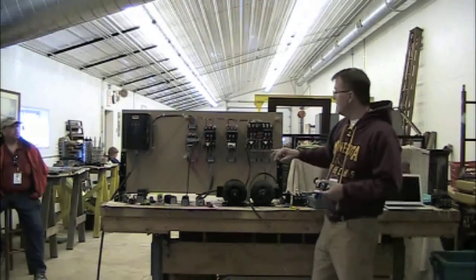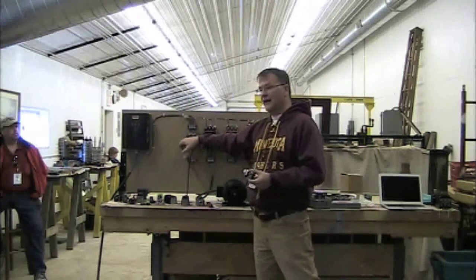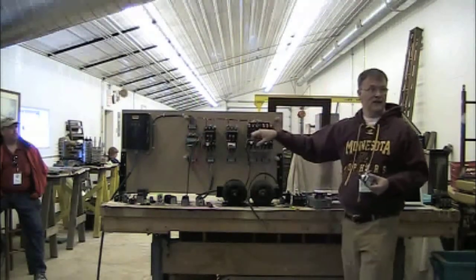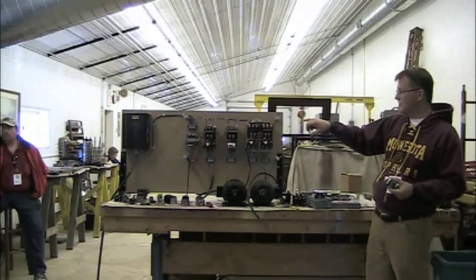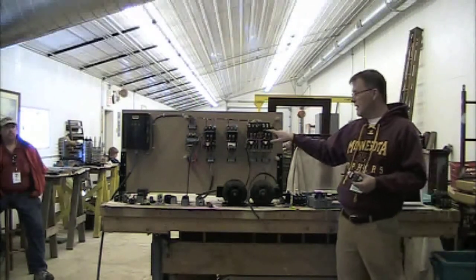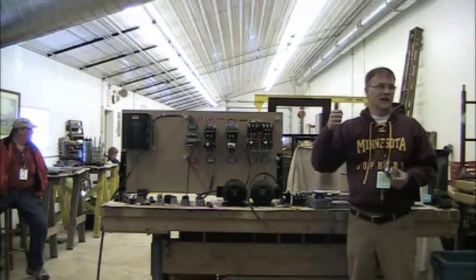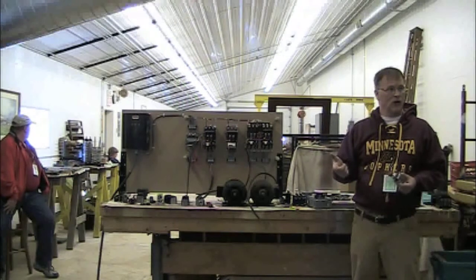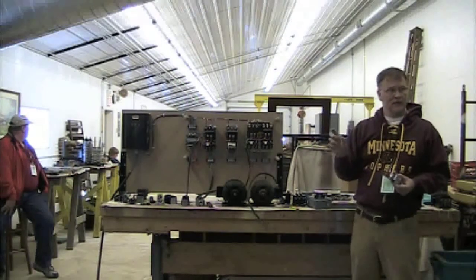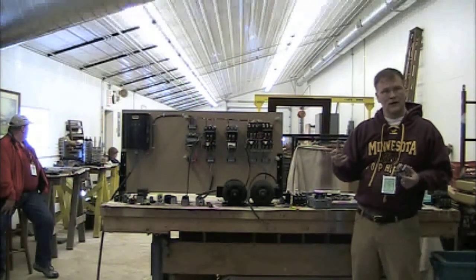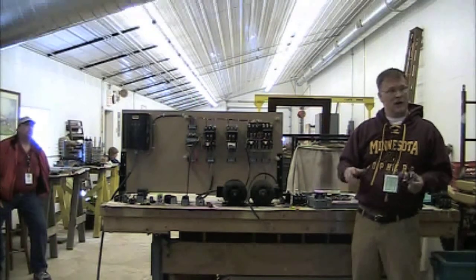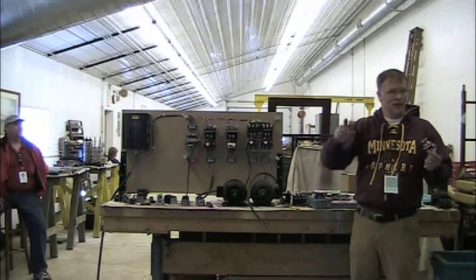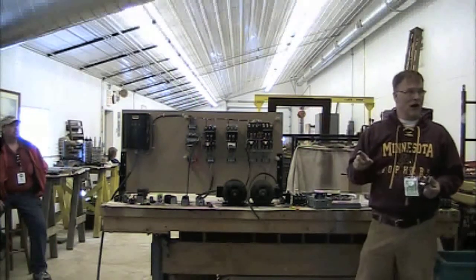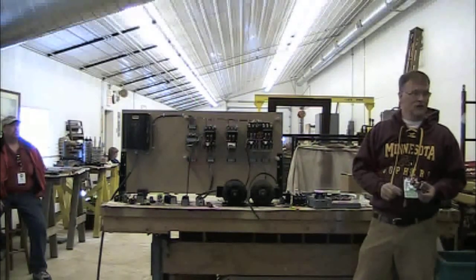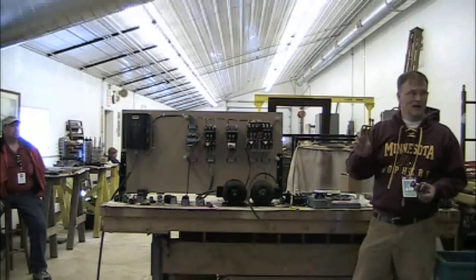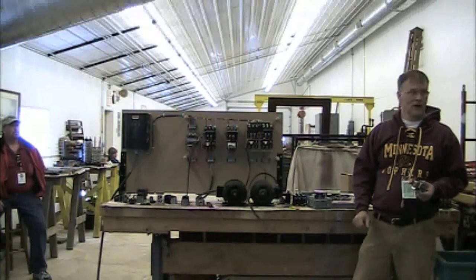But you need to size them. These are rated in volt-amp ratings, and you need to size the transformer. If you go look, all the manufacturers will give you the inrush and the sealed coil burden in volt-amps. If you're only doing a single coil, it's easy. But if you're running a bunch of things off of it, like the relays in my phase converter, I need to know the draw on every one of those things so that the control transformer is sized adequately to run all of the control circuits.